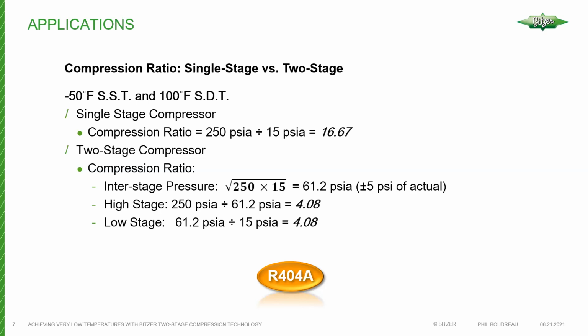The two-stage compressor, because we've got two stages to make up this overall compression process, looks something like this. We have the same high side or discharge pressure of 250 PSIA, and the low side or suction pressure is 15 PSIA. To calculate the approximate interstage pressure for a 6-cylinder compressor, we multiply the two absolute pressures, suction and discharge, together and take the square root of that number. In this case, it works out to 61.2 PSIA. This will get you within plus or minus 5% of the actual number that you'll find in the software.